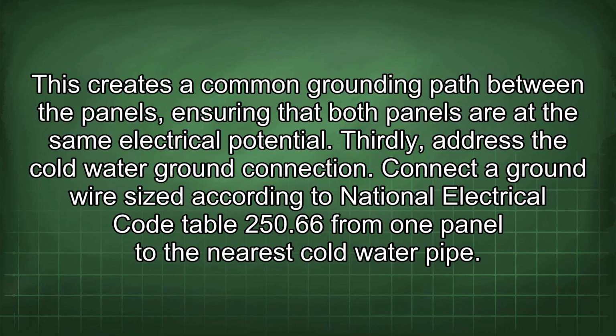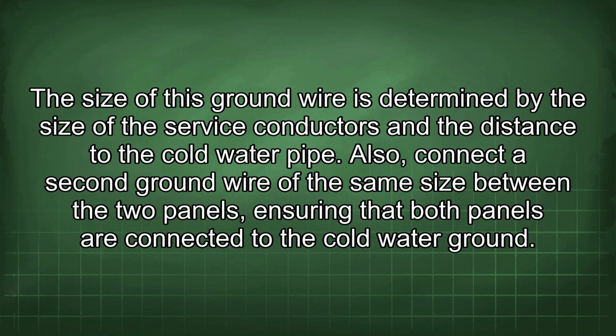Thirdly, address the cold water ground connection. Connect a ground wire, sized according to National Electrical Code Table 250.66, from one panel to the nearest cold water pipe. The size of this ground wire is determined by the size of the service conductors and the distance to the cold water pipe. Also, connect a second ground wire of the same size between the two panels, ensuring that both panels are connected to the cold water ground.